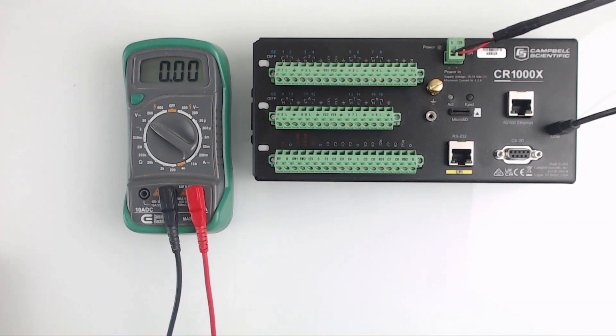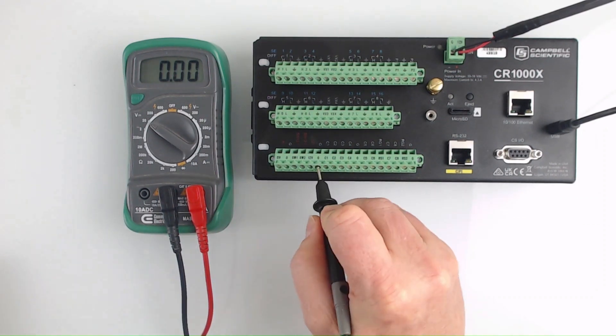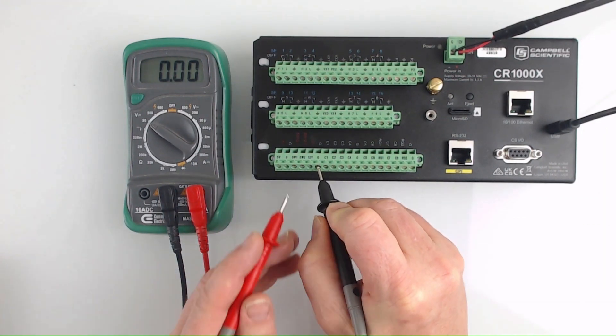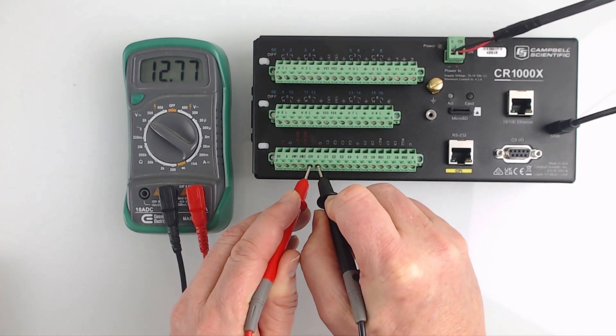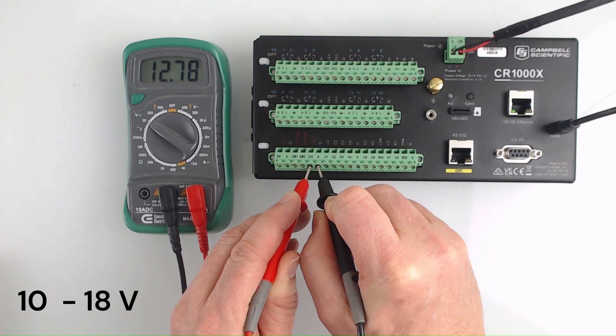Touch the black probe to the terminal screw for any channel labeled G, and the red probe to the terminal screw for the channel labeled 12V. Some data logger models don't have a 12V channel, but have an equivalent channel labeled BAT+. The reading should match the voltage coming in from the power supply and be within the data logger's operating range. In this case, the CR1000X has an input voltage range of 10 to 18 volts, so this reading indicates that the data logger's power is okay.